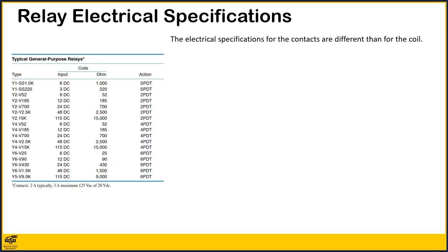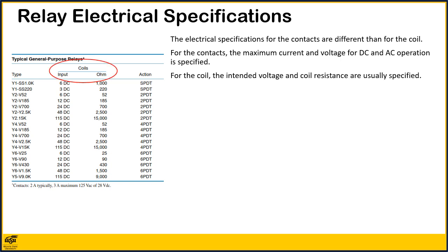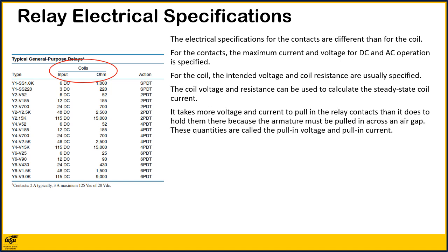The electrical specifications for the contacts are different than for the coil. For the contacts, the maximum current and voltage for DC and AC operation is specified. For the coil, the intended voltage and coil resistance are usually specified, and you can see these numbers on the spec sheet shown in the table. The coil voltage and resistance can be used to calculate the steady-state coil current. Actually, it takes more voltage and current to pull in the relay contacts than it does to hold them there, because the armature must be pulled across the air gap. Hence, these quantities are called respectively the pull-in voltage and the pull-in current.